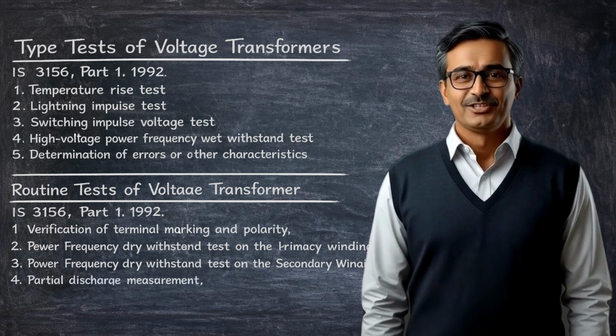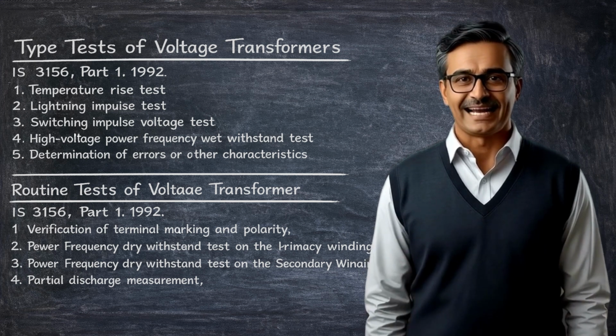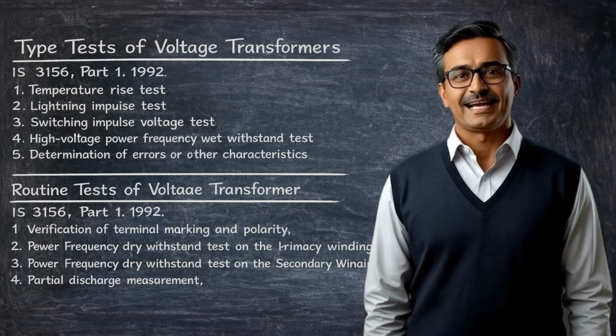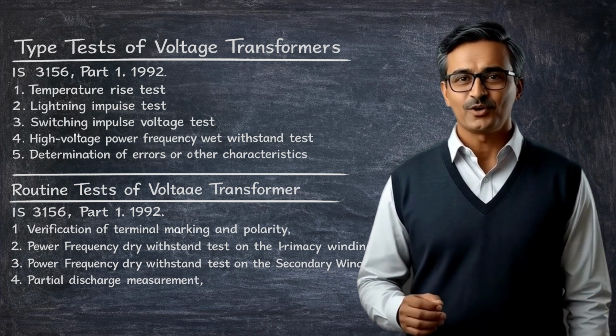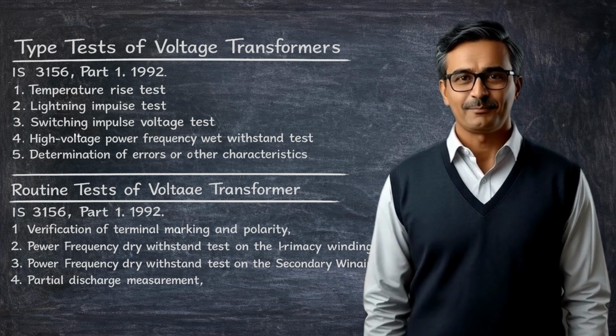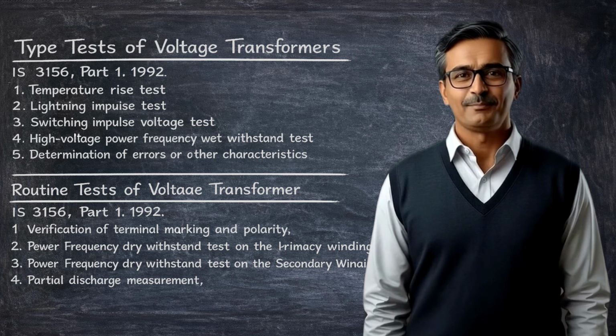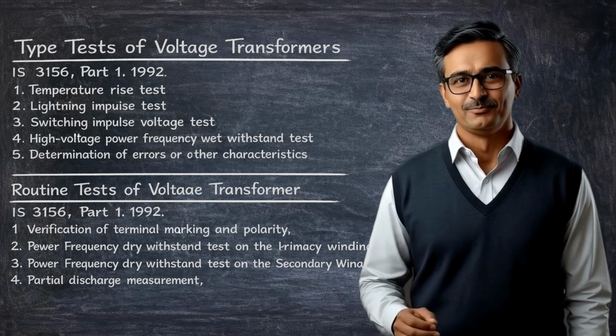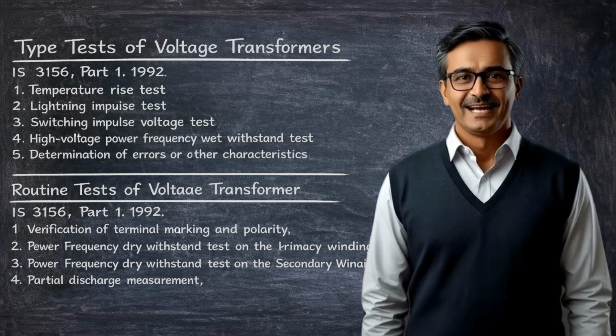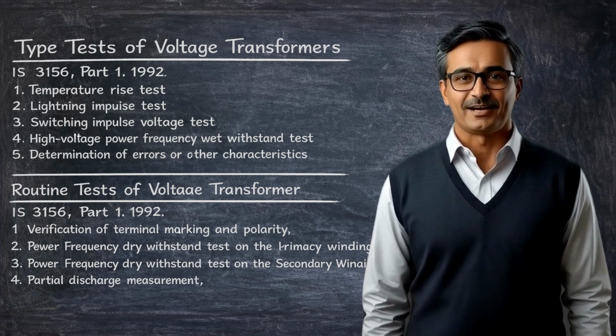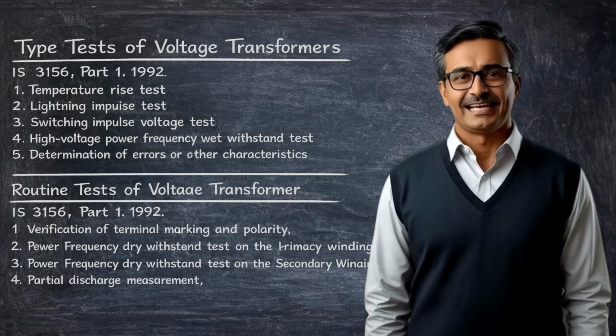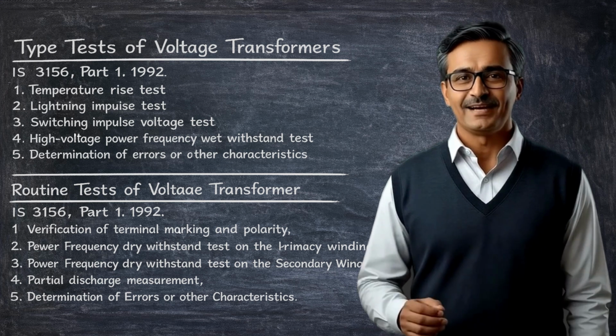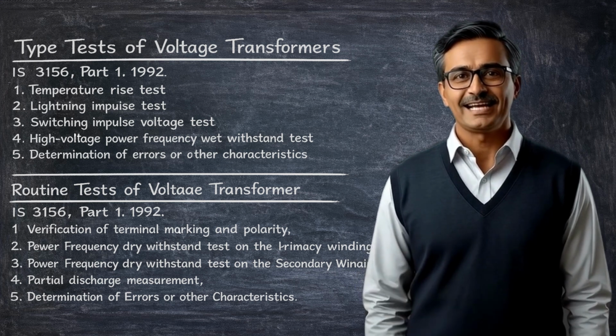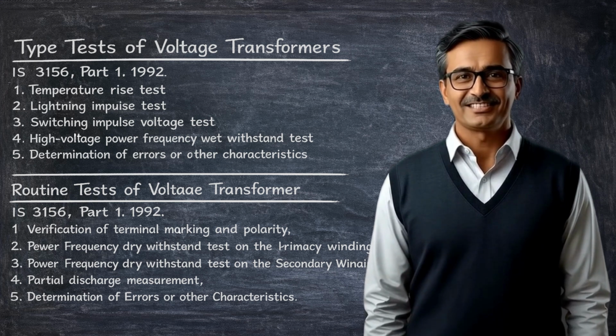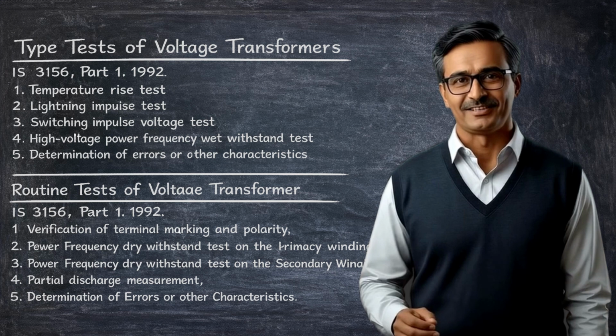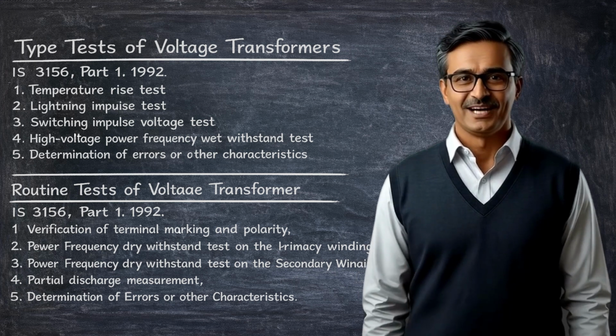The fourth test is partial discharge measurement, which is carried out according to IS 11322, published in 1985. However, there is an important note regarding this test. This test is applicable only to voltage transformers that have oil-immersed insulation and are designed for highest system voltages of 72.5 kV and above. This test is not applicable to capacitor voltage transformers, also known as CVTs. The fifth routine test is the determination of errors or other characteristics. This test checks whether the transformer meets the required accuracy class or designation specified in the relevant part of the standard.